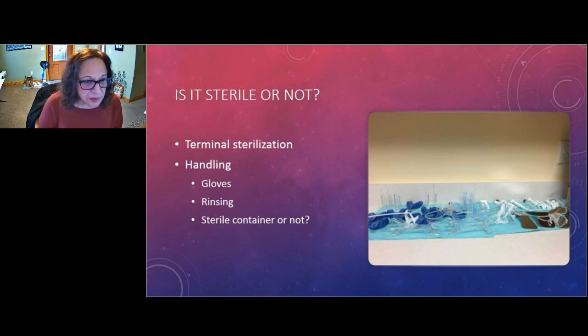Again, some of the literature will tell you that, for example, hydrogen peroxide has a good log reduction as a sterilant, even at 6 hours. But glutaraldehyde may take 10 hours or longer and may not necessarily achieve the same level, the same log reduction level of microbial activity. So why are they doing it? Beats me.